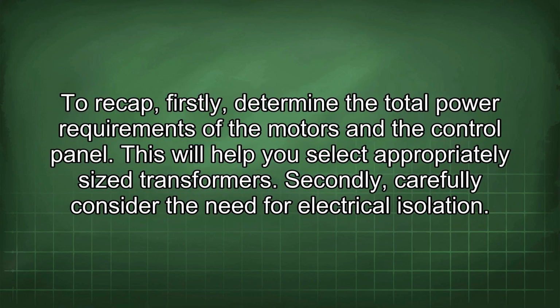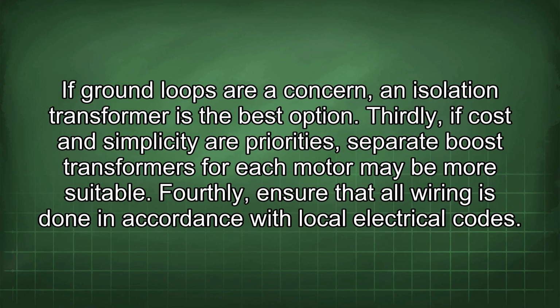To recap, firstly, determine the total power requirements of the motors and the control panel. This will help you select appropriately sized transformers. Secondly, carefully consider the need for electrical isolation. If ground loops are a concern, an isolation transformer is the best option. Thirdly, if cost and simplicity are priorities, separate boost transformers for each motor may be more suitable.